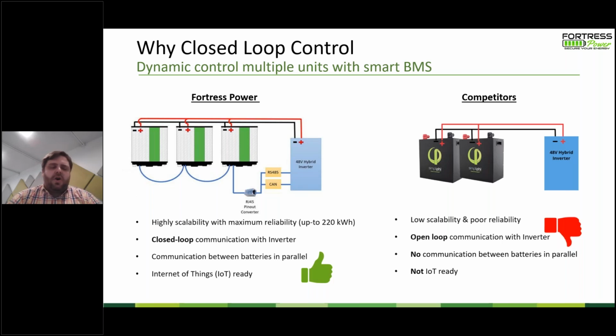It's like driving a car with upgraded brake pads so that you can accelerate and decelerate more quickly when the battery talks directly to the inverter. When the battery doesn't talk directly to the inverter, the inverter is driving the battery usage, and so you have to have a little bit more of protective gloves on when you're dealing with the charge and discharge circuits. So that means you can get a little bit more power and operate more closely towards the maximum rating of the battery rather than the recommended rating of the battery, and still maintain the warranty when you have closed loop.